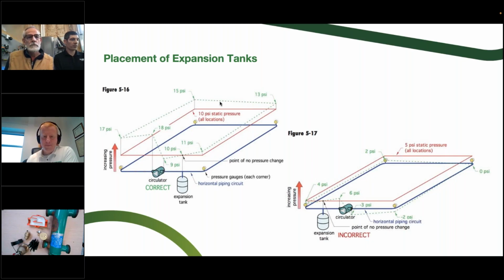So the pressure is going to start to drop as it comes around the bend, goes through the different fittings, and comes back. We're down to 9 PSI before it's boosted up again. There's your point of no pressure change, right where the expansion tank connects. What changes when we have an expansion tank that we're pumping into? Do you want to walk us around the loop here? Yeah, and it's going to depend both on the circulator and the loop itself.